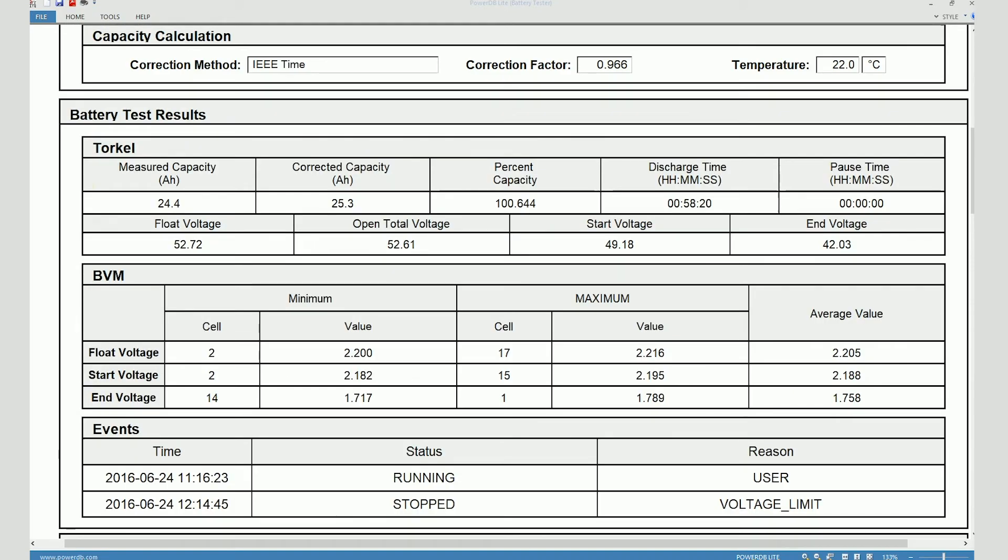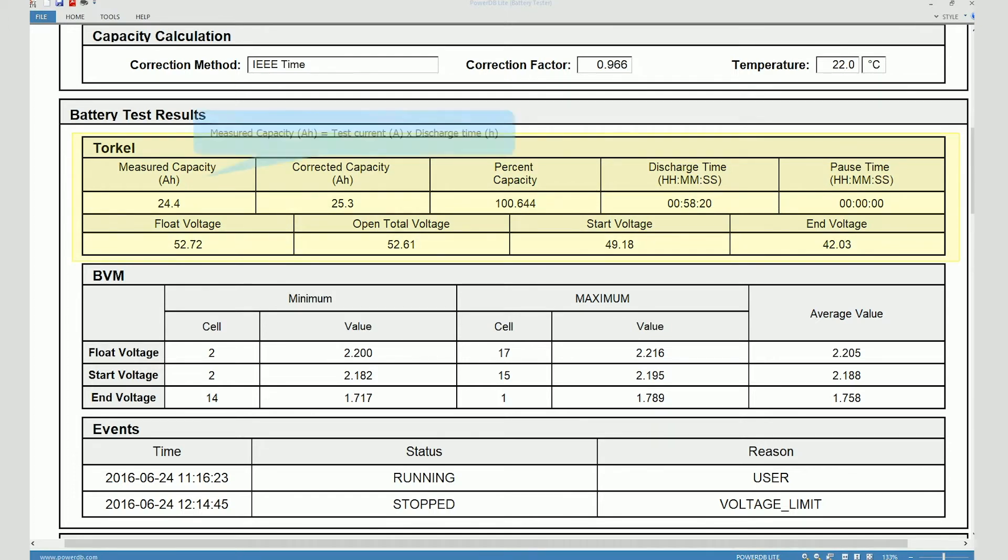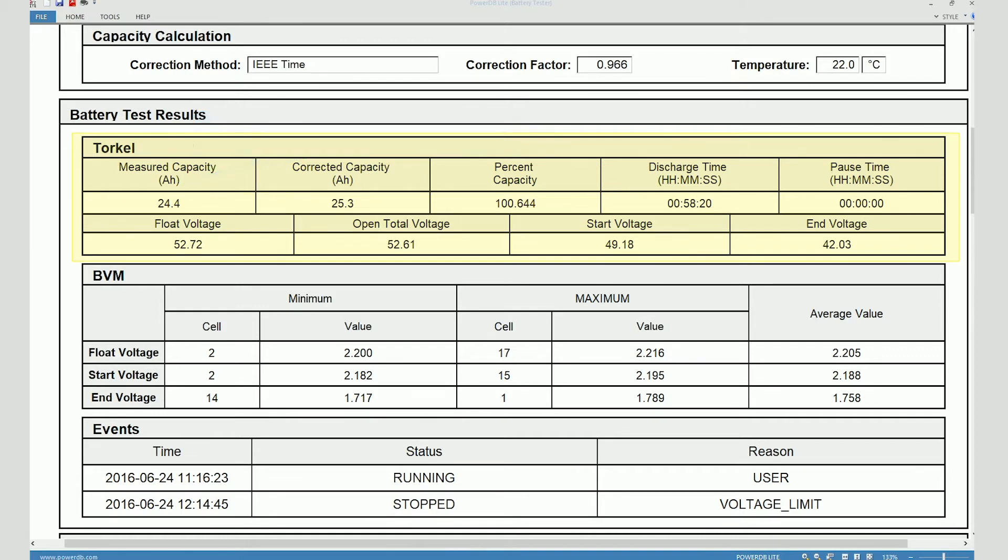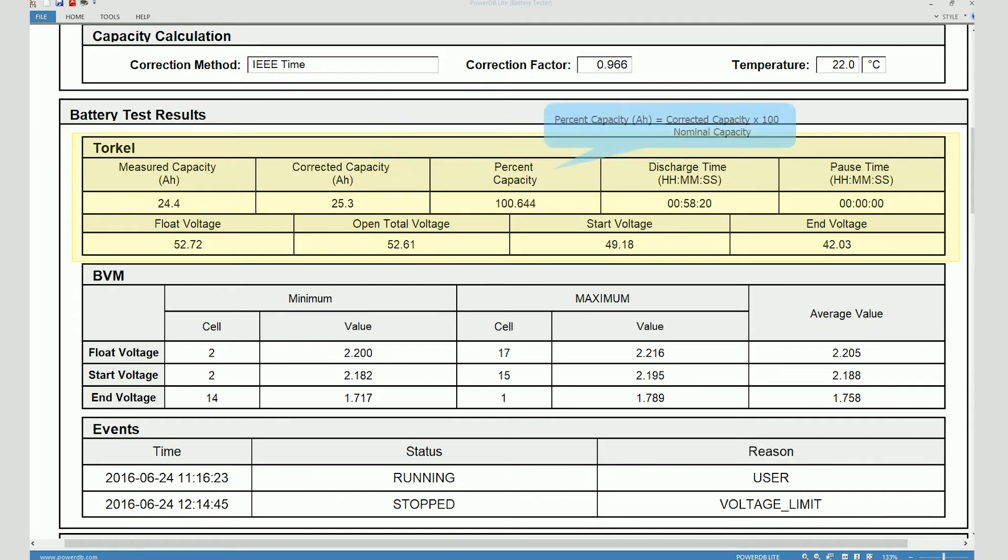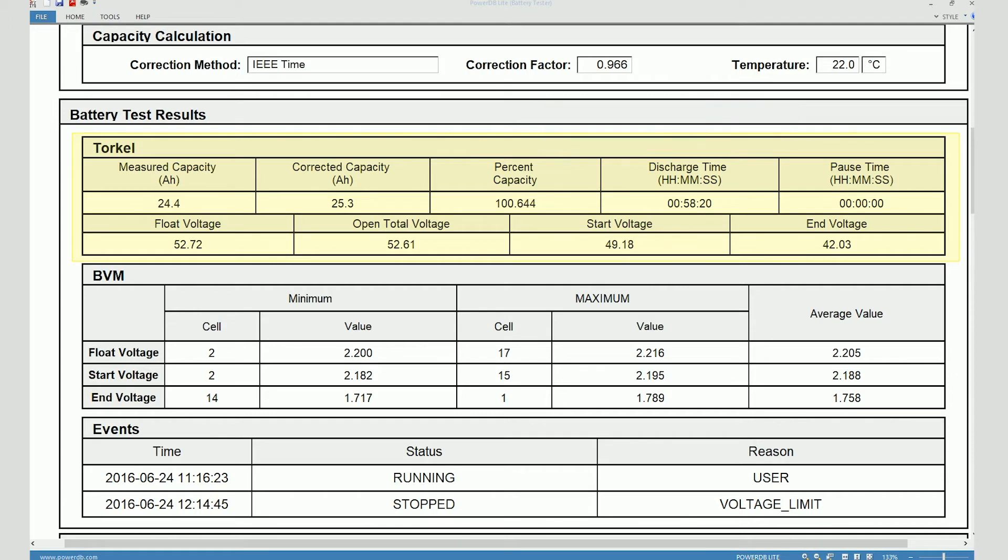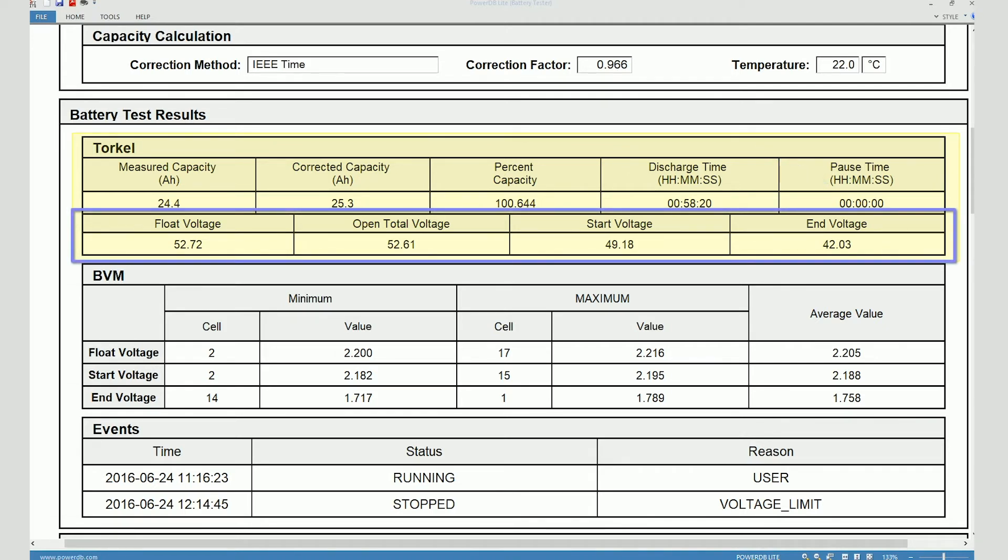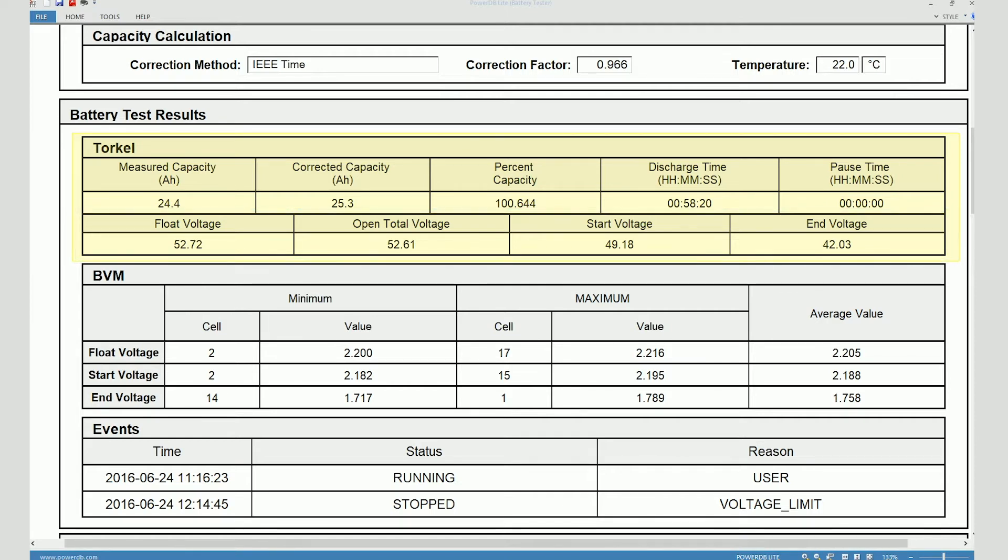If you scroll further down you see a summary of the discharge test results. The overall battery voltage test results are shown here where you can see the measured capacity which is test current times the actual test duration. Corrected capacity takes the temperature correction factor into consideration. The capacity is shown in terms of percentage. Here you can see the actual test duration which is 58 minutes and 20 seconds. Pause time is 0 which means the test wasn't paused midway. The float voltage is shown, the open voltage and the start voltage and the end voltage. These are all overall voltage values.